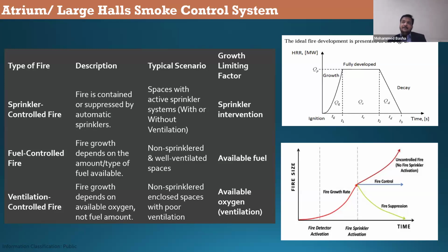So for example, if a fire is happening in an enclosure, in a space where you shut down all the windows and doors, what happens? The fire will still burn until the available amount of oxygen within the space is used. And once the byproducts of fire are released, which is the carbon monoxide, carbon dioxide, whatever comes out of the fire, that will fill the room and it will displace the oxygen.